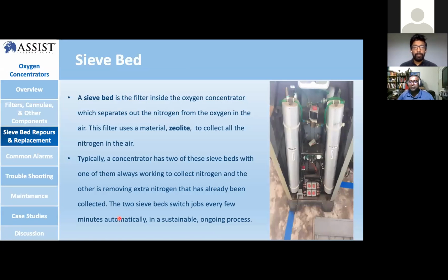So now we're going to talk about sieve beds. A sieve bed works like a filter inside the oxygen concentrator that separates nitrogen and oxygen in the air. The basic idea is that you give a pressure of air into the sieve tank, and it absorbs the nitrogen and releases the oxygen at the top of the system. In a typical oxygen concentrator, you're going to see 2 sieve beds. That's very common. And it's very important that both sieve beds are in good condition to get equal output. Sometimes you get 1 sieve bed broken. The other one is good, but you still don't get a good reading because it doesn't perform very well. So you have to look into that part as well.